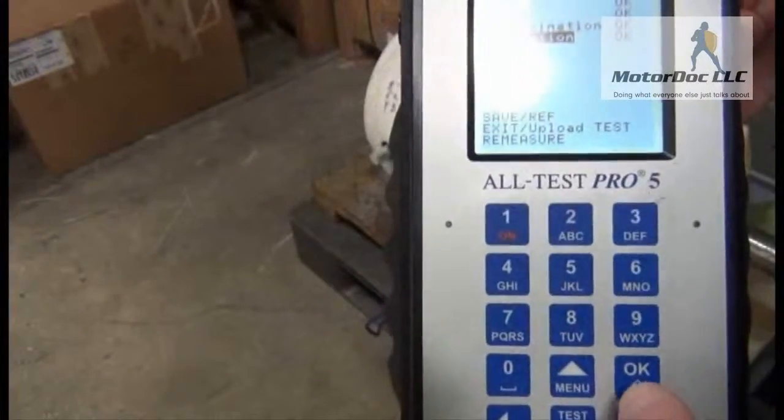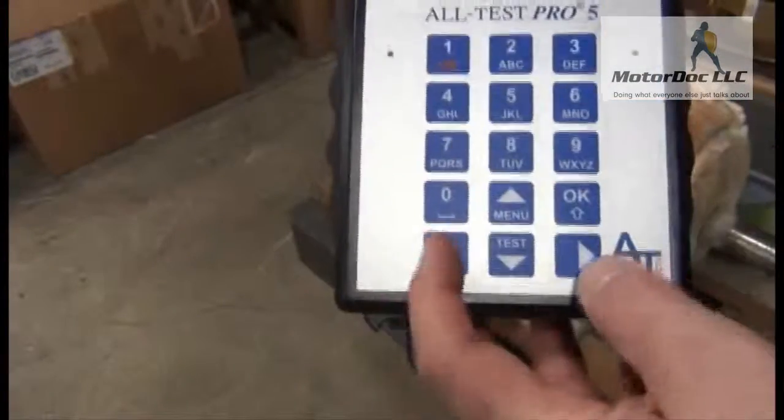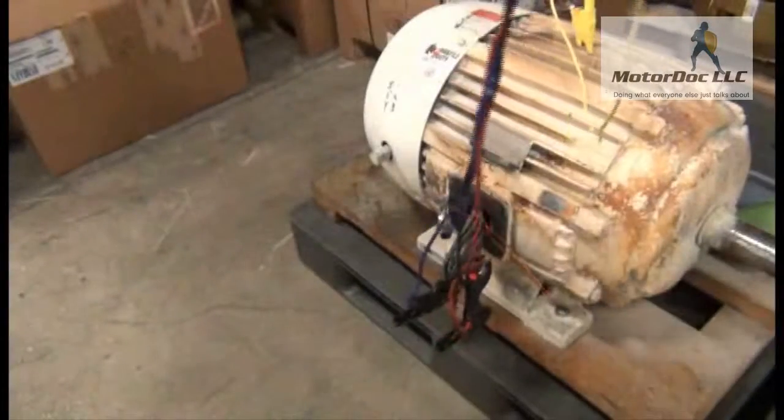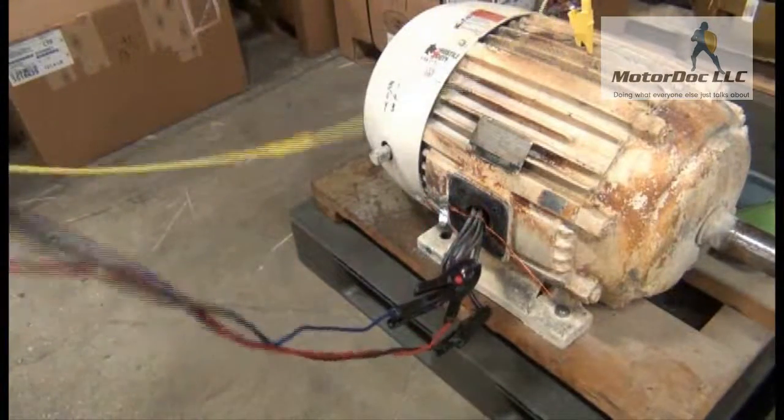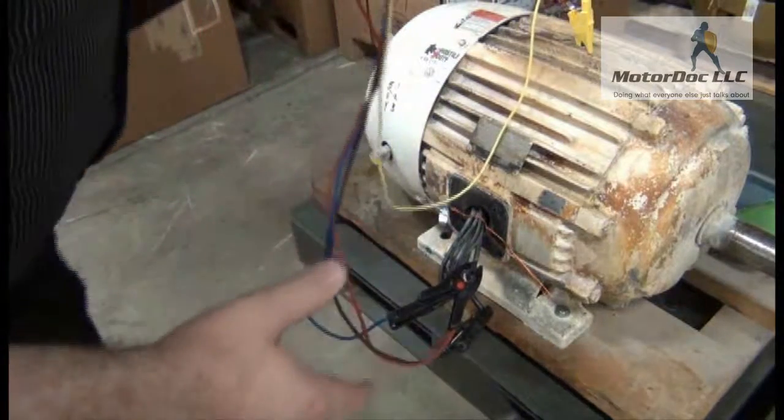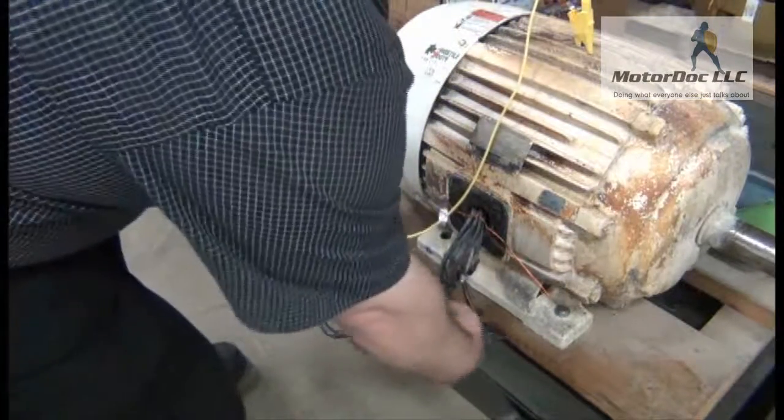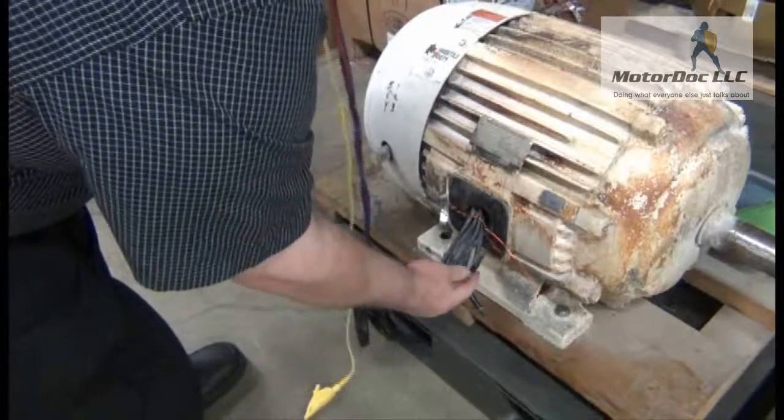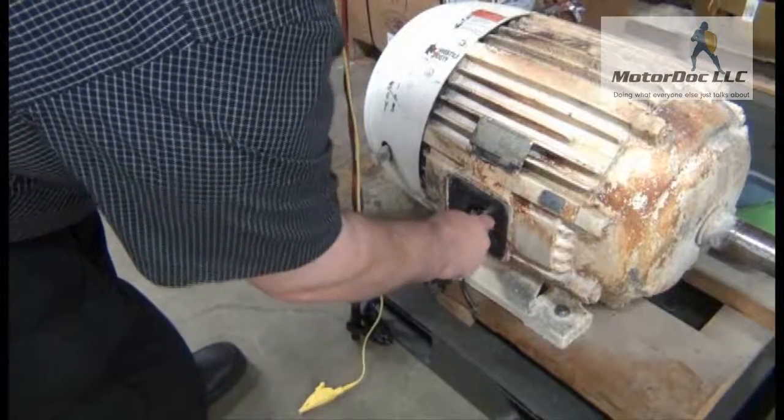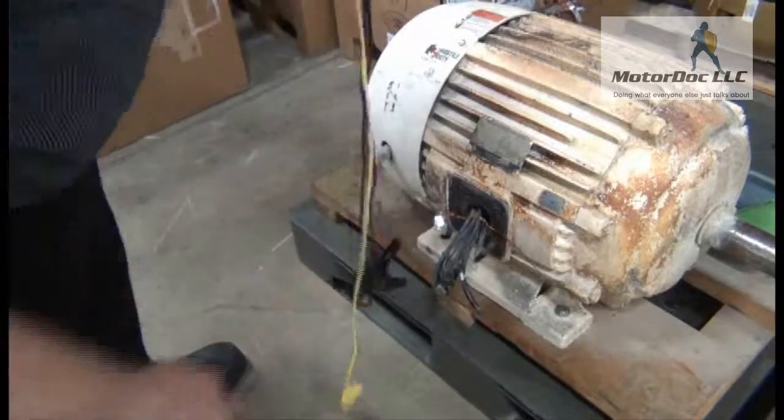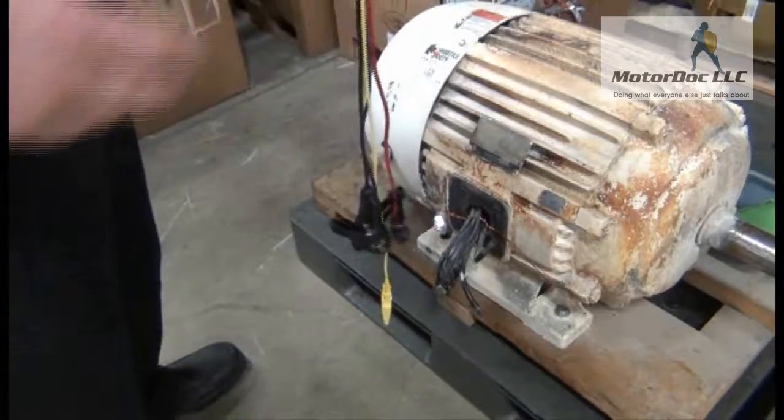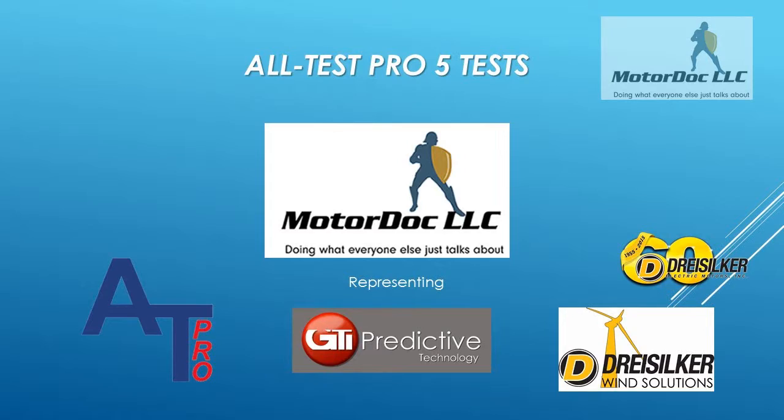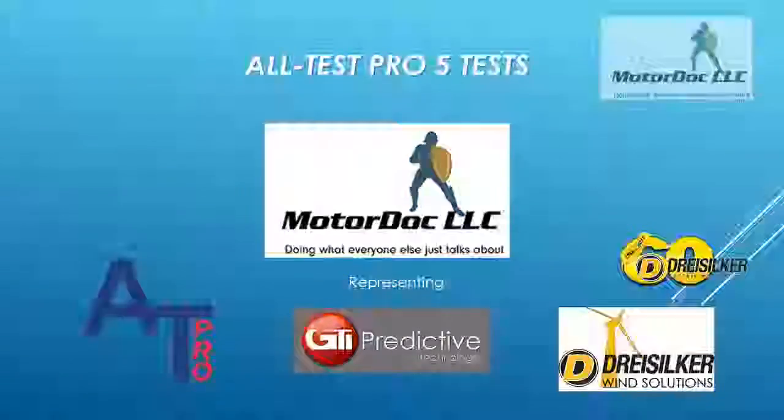Now let's go ahead. And we are going to return in, I'm lazy. So I like to use a shortcut. There we go. Now what I usually recommend is that, regardless of the test you perform, it's right after, you verify that it's grounded. For a machine of this size, I'm just going to basically touch ground and make sure I don't have any power there. Otherwise, it'll cause my insulation resistance test to trip.